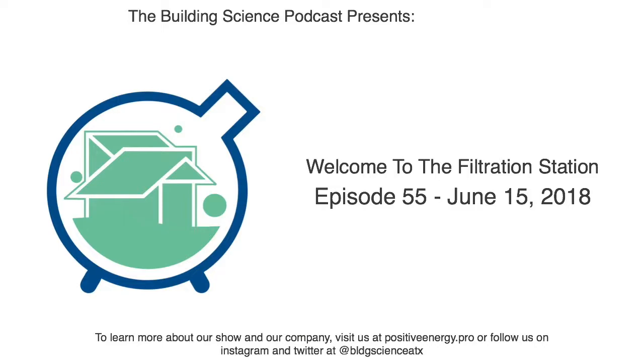So if you do go to Home Depots of the world, people have come up with their own, clean air delivery rate or some other method, it's more of a help to a consumer understand. The hard part to teach someone about filters is it's not about just MERV. It's about filter efficiency. It's about life of a filter or dust holding capacity, and it's about pressure drop. And you kind of have to balance those things for your needs. For example, you can have a good, what's called a MERV 14 1-inch filter, and it only lasts a month before it plugs up, right? So it had a higher initial pressure drop. It had a great MERV number, but it had poor life.